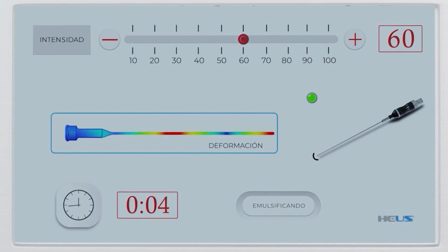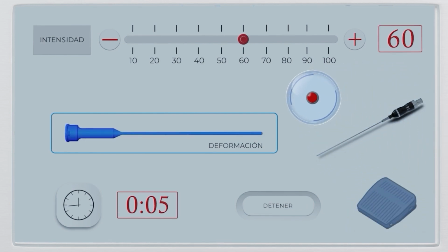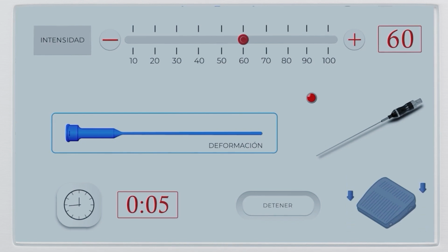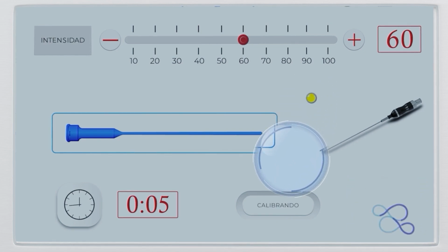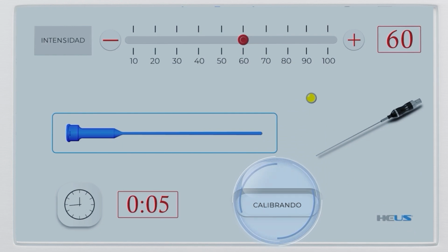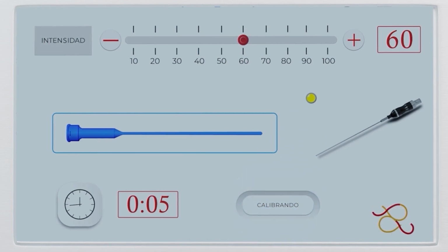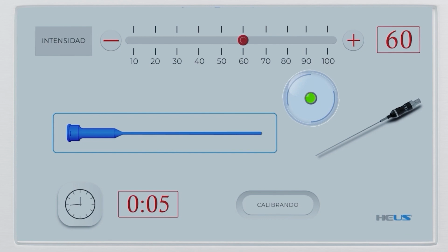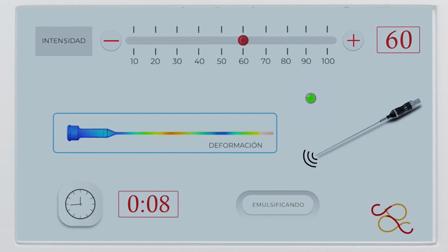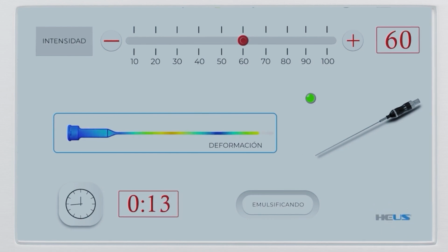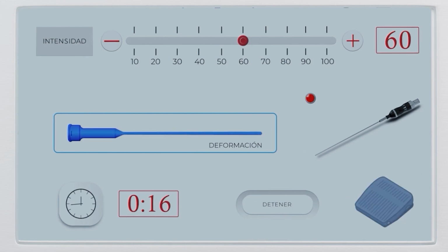On the right side of the screen, an animation of the handpiece and a red LED in a flashing state will be displayed, indicating that the equipment is not in operation. When the foot pedal is pressed, the flashing red LED will change its color to yellow. At the same time, the device will adjust the power to the one previously selected. This process will last approximately 10 seconds. After this, the LED will change color to green and will continue flashing. This will mean that the device is now working. Once you decide to release the pedal, the device will return to standby mode, red LED.